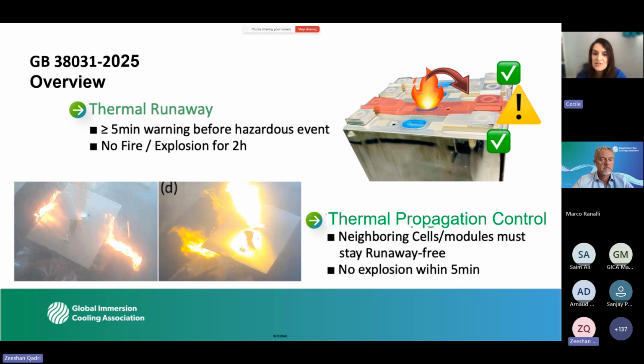The second one is thermal propagation. When you trigger on purpose a runaway or failure on a cell, you need to make sure the neighboring cells and module stay runaway-free, with no explosion for 5 minutes. This drives the usage of technologies like aerogel, mica, or maybe some foam in between the cells in order to isolate one problem from the neighboring cells.